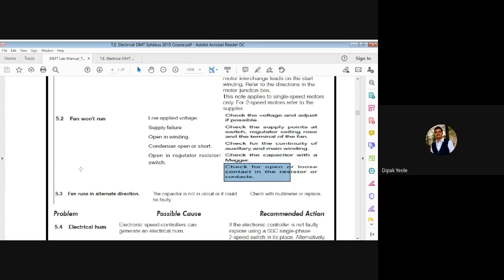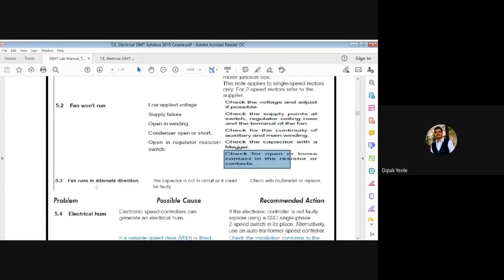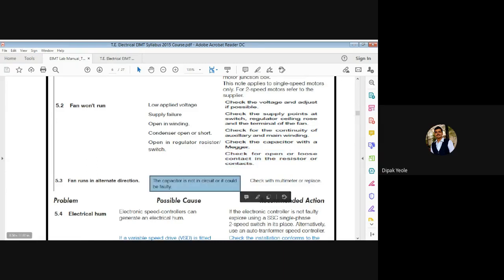The third problem is fan runs in alternate directions — meaning it runs both clockwise and anti-clockwise. The cause can be that the capacitor is not in circuit or could be faulty. Check with a multimeter, and if faulty, replace the capacitor.